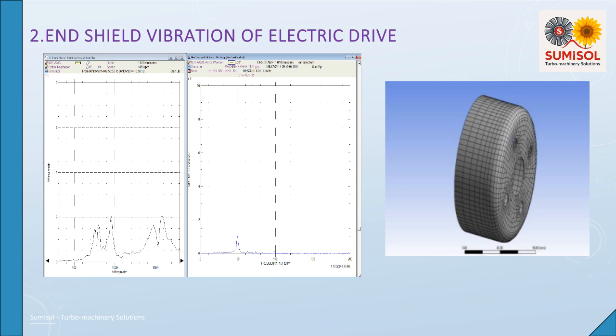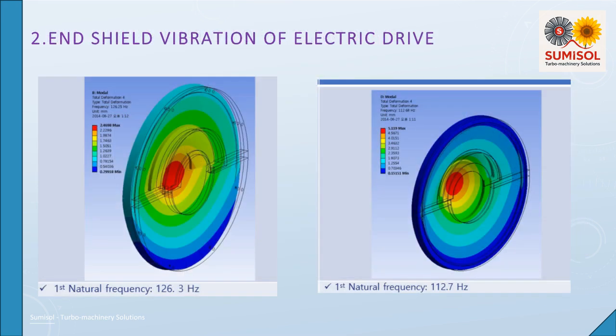The levels exceeded the IEC 60034-14 grade B acceptance criteria of 1.5 mm per second RMS for solo run test. The first natural frequency of the end shield was found to be around 120 to 124 Hz, which was in resonance with the 2 FL excitation force from the motor. For this reason, the axial vibration level on the bearing housing reached 7.5 mm per second RMS. By adding mass as a horizontal bar, the overall first natural frequency came down to 112 Hz. Another simulation was done to remove mass, creating holes, to reach 110 Hz. However, addition of a stiffener was considered in execution as a stop-gap arrangement till the new end shield was dispatched to site.